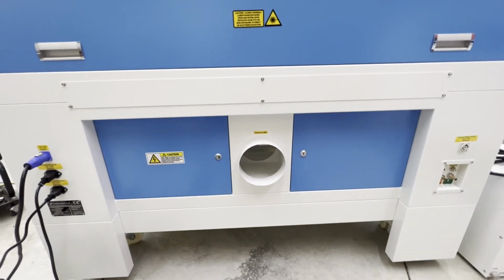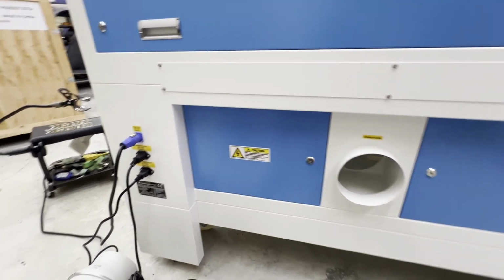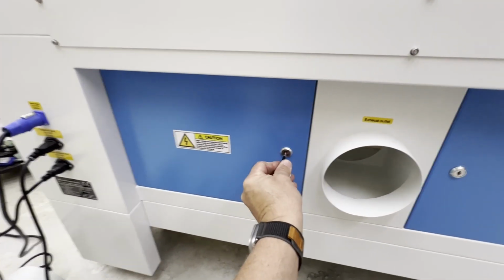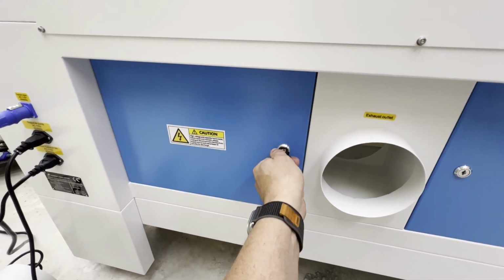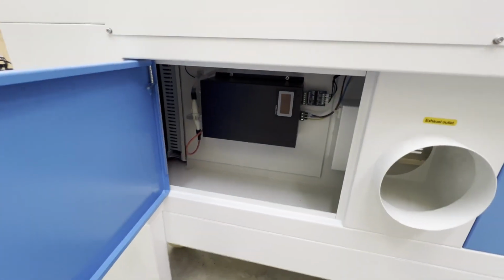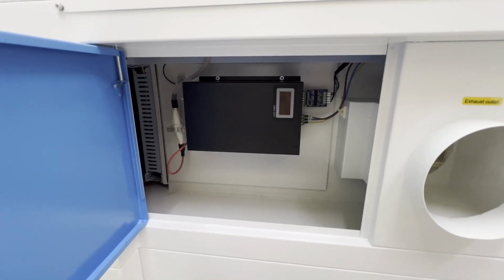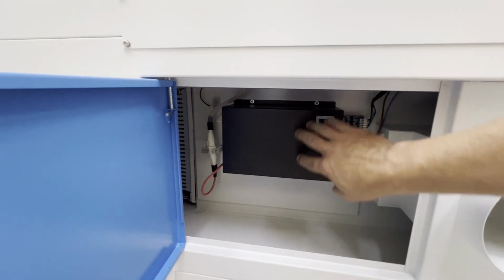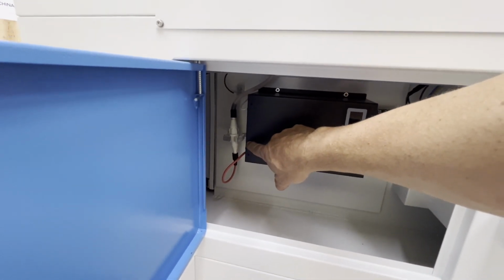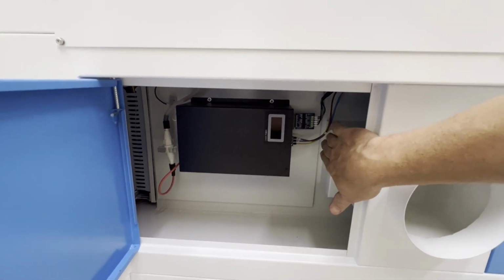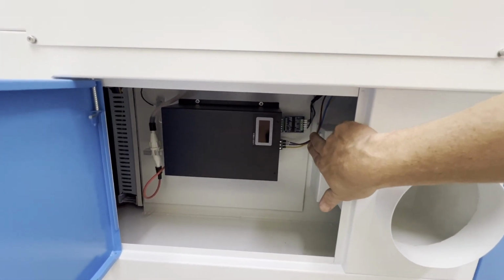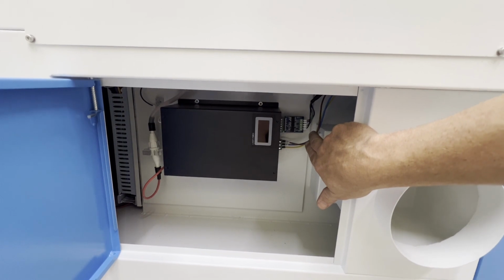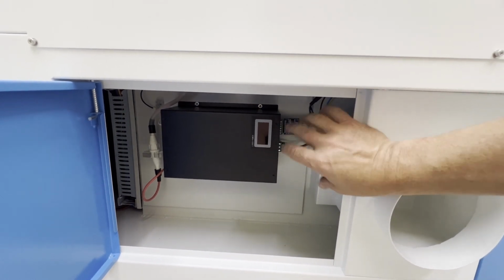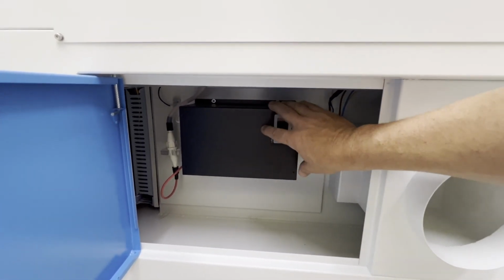On the back side we have 2 doors, one of which will have our LPSU, which is our laser power supply, in the back. We have our laser power supply, our high voltage connector, that white one with the red wire. We have our incoming power, and then we have our opto board, which is an optical isolation so that there's no feedback going. This is a very, very high voltage.